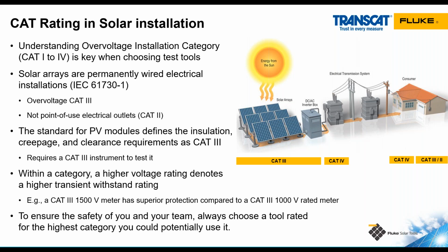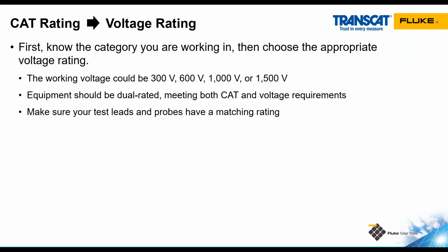So we need to know what environment we're working in. In solar, if you're working on a PV array, that's a category 3 environment. If you're working on the electrical system on the AC side, close to the utility, that's going to be a category 4 environment. Once we know the category ratings, we need to know the voltage of the system that we're going to be working on.